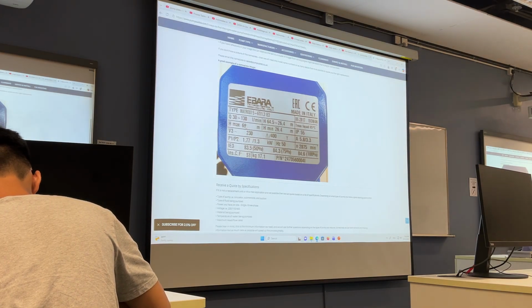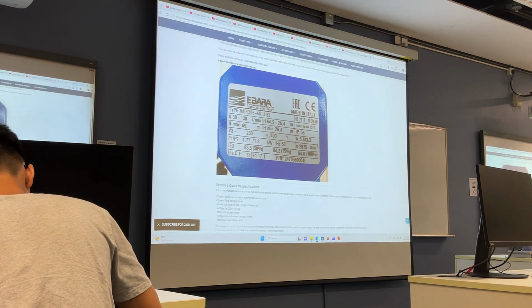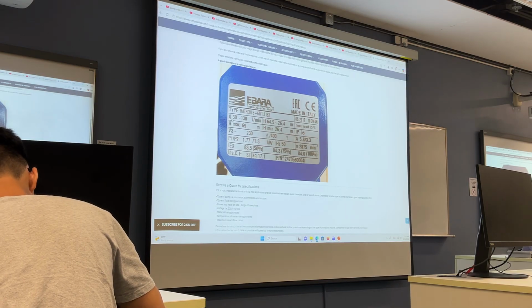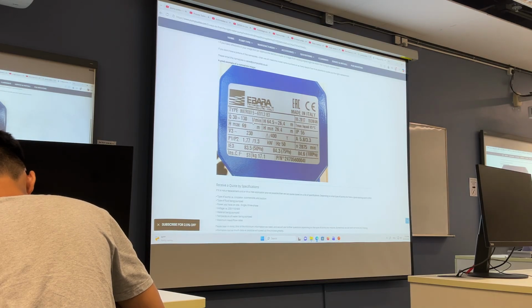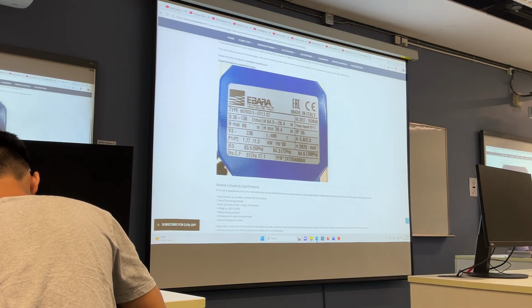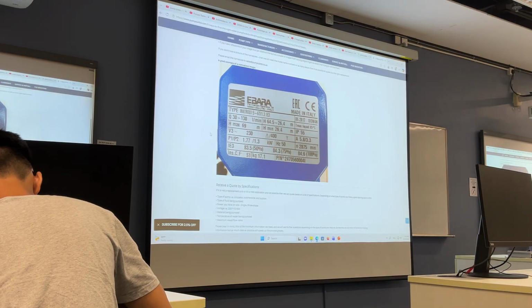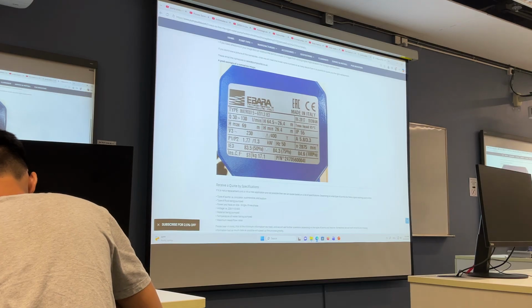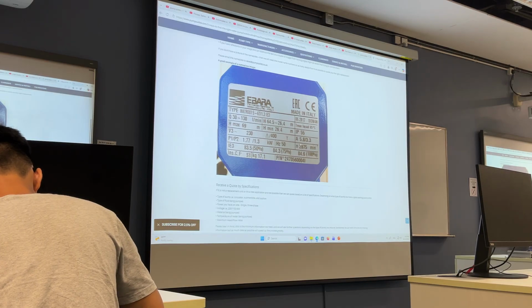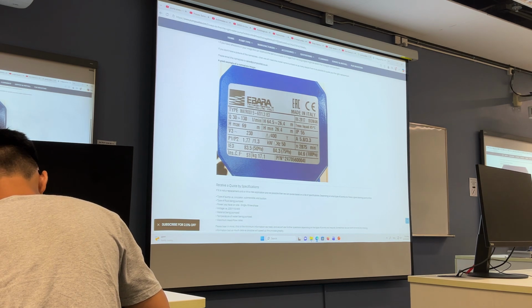It has a range: the minimum is 26.4 meters and the maximum is 69 meters. And the discharge is 30 liters per minute to 130 liters per minute. You can also see the rated power. The N is the revolutions per minute. The working condition for the pump is 50 hertz. The revolutions per minute is the RPM.